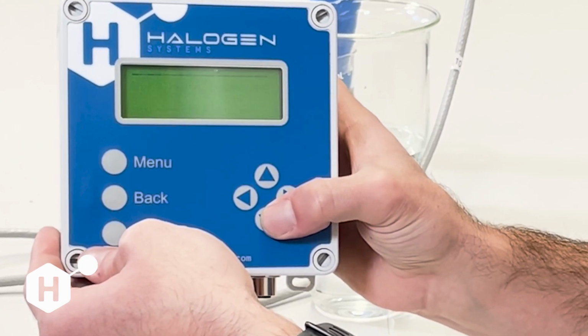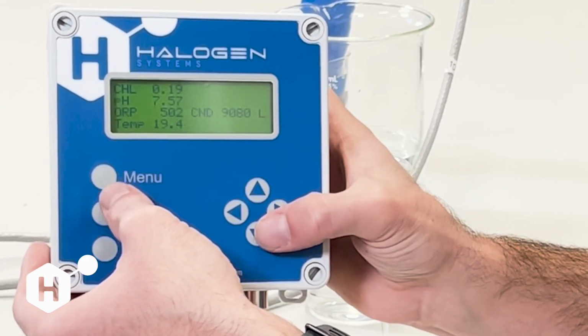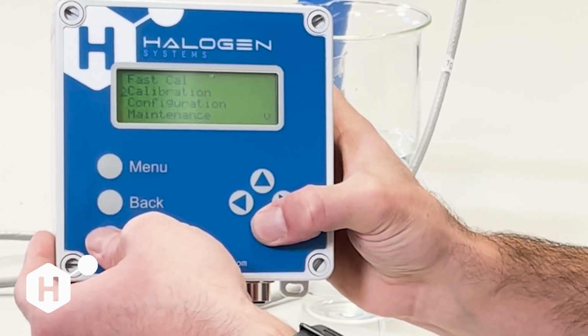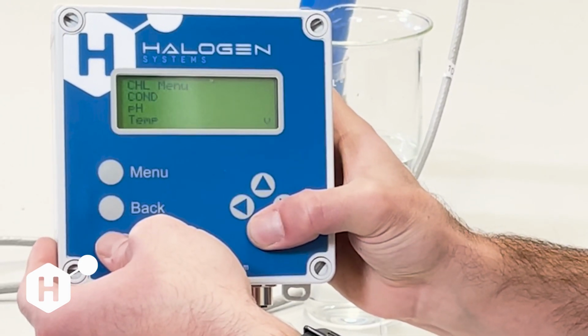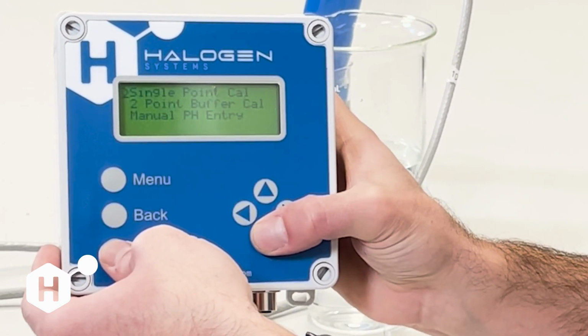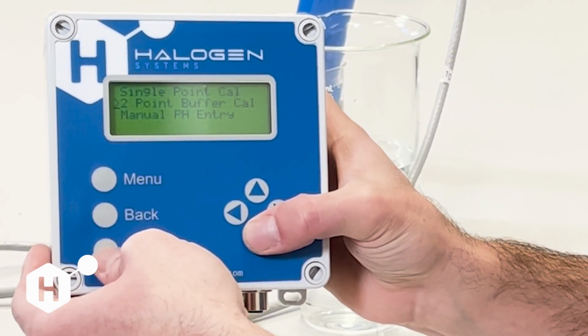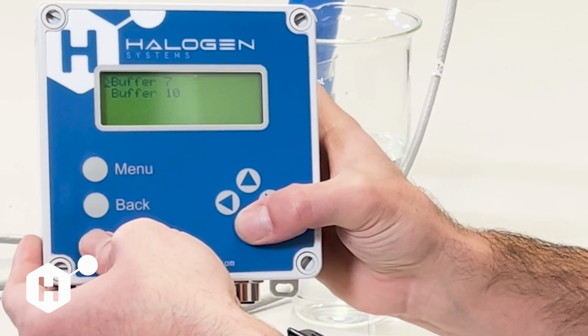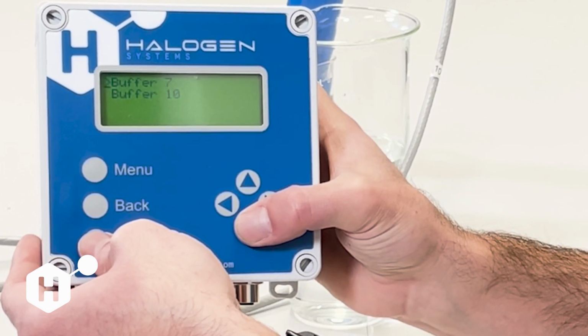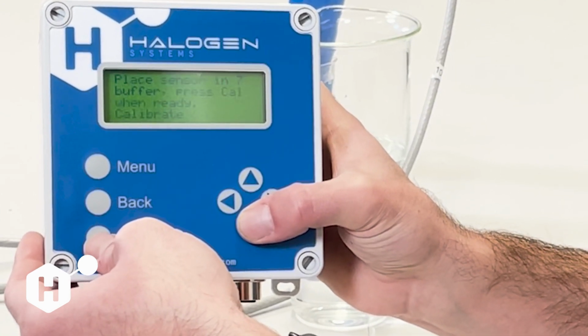We'll get our confirmation that it's selected, the little L in the corner. We're going to go to Menu, Calibration, pH, and then we're going to go to 2-point buffer calibration. The first one that we're going to complete is the pH 7 buffer calibration. We're going to hit select.